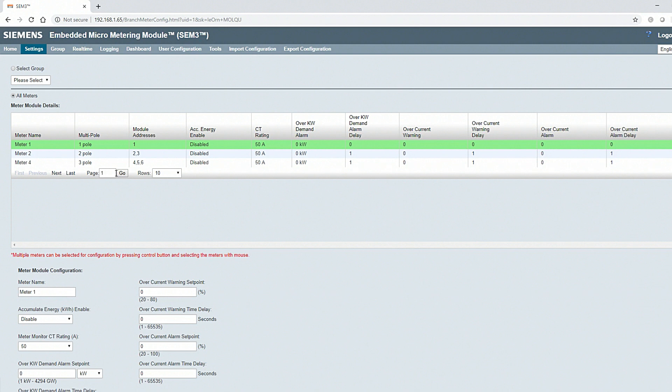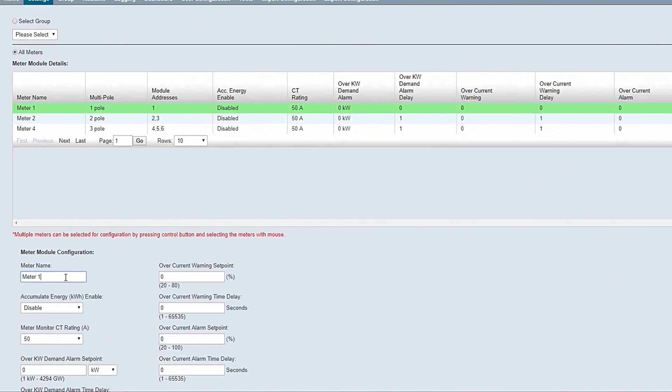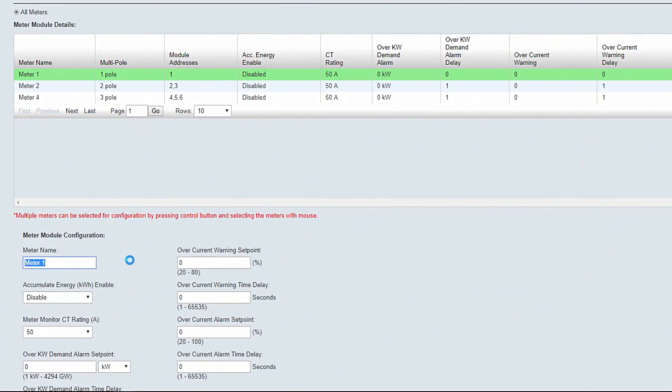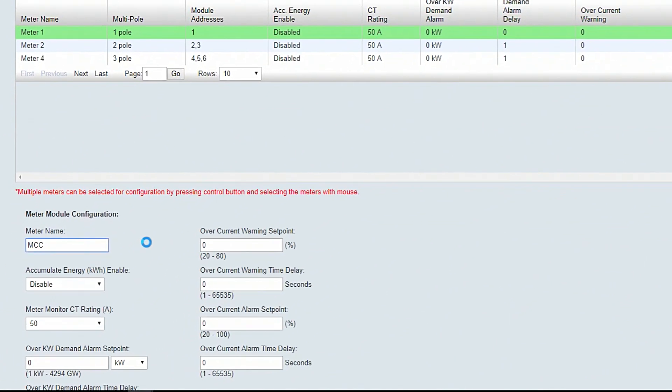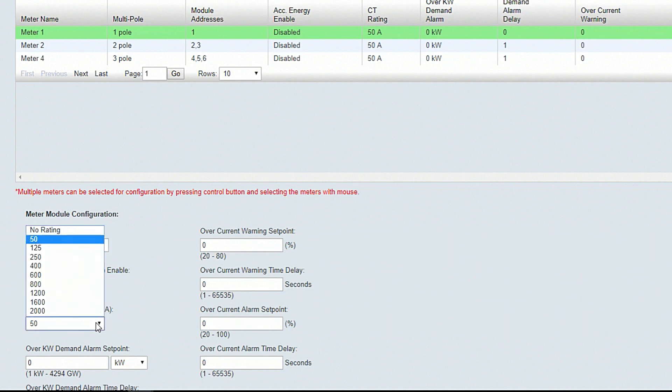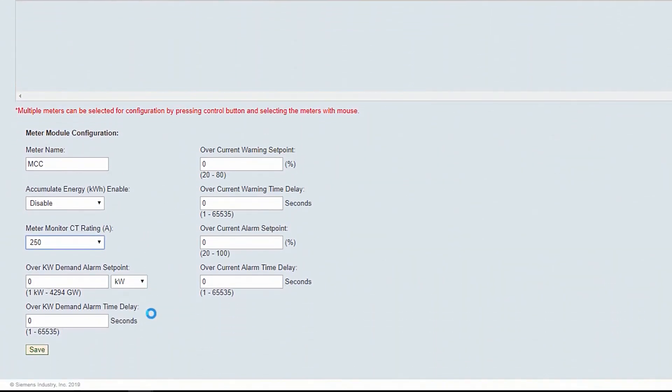When a meter is highlighted, the configuration menu will appear. For this example, we will name our one-pole meter MCC and select a 250 amp CT. When the branch meter configuration is complete, click Save.